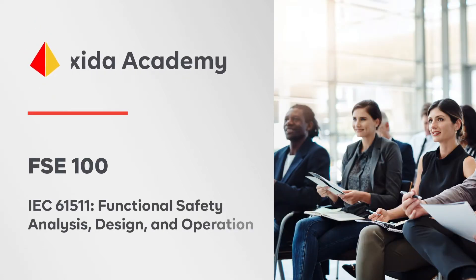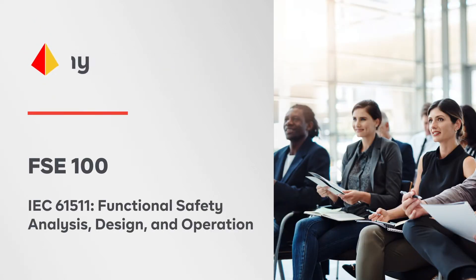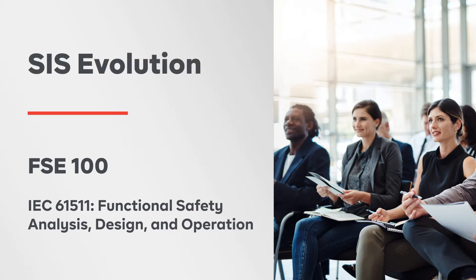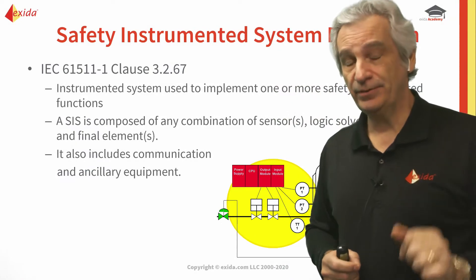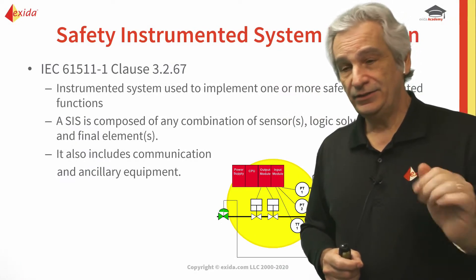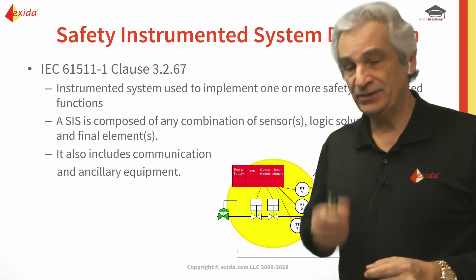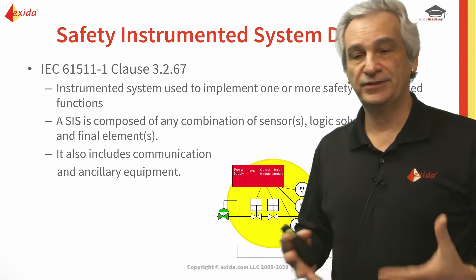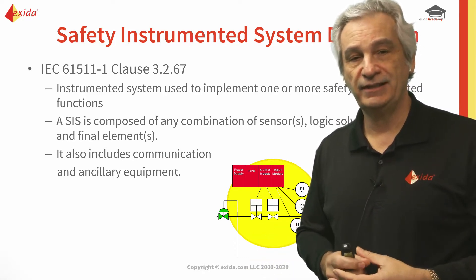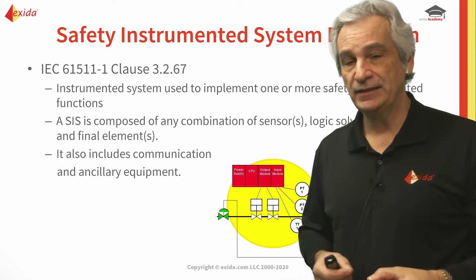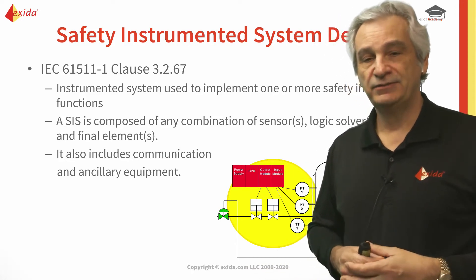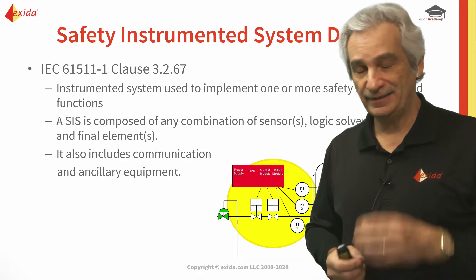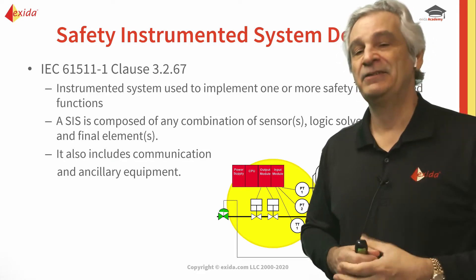IEC 61511 clause 3.2.67 defines a SIS as an instrumented system used to implement one or more safety instrumented functions. This is very important because I can usually tell how well versed end users are in the standard — if they tell me it's a 'SIL2 system,' they really don't know.